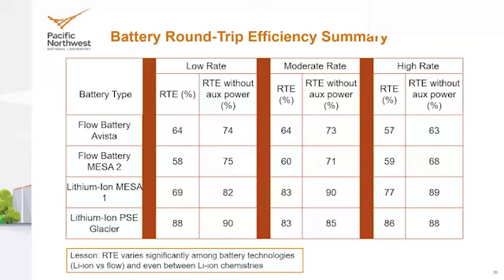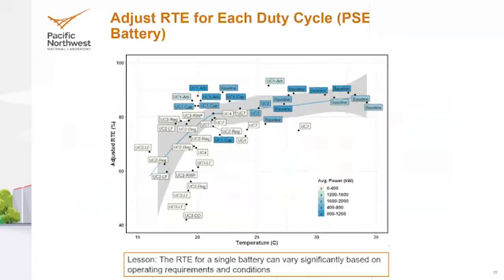This is a simple test showing a low rate of output, moderate rate, and high rate of output. You can see for one lithium-ion battery system, the round-trip efficiency went from a low of 69% all the way up to 90%, while the other at Puget Sound Energy was much more uniform, from 83 to 90%. The flow battery systems yielded lower round-trip efficiency rates, and we found when testing under certain conditions that the round-trip efficiency could fall even quite a bit lower, down into the 40% range. So it's important to adequately and accurately characterize the performance of these energy storage systems.